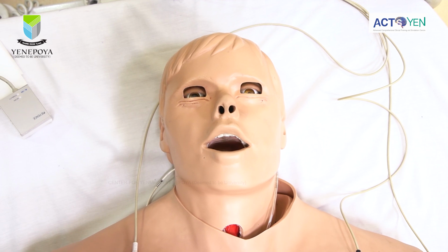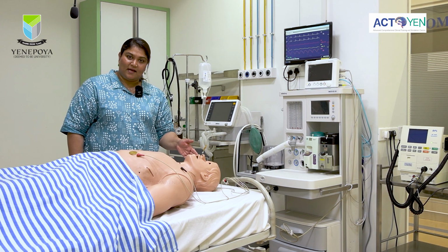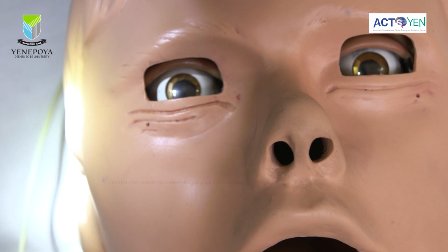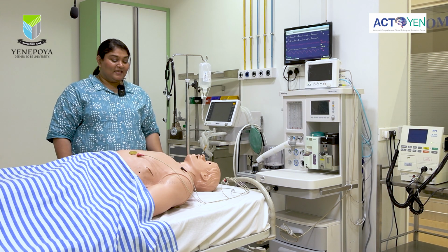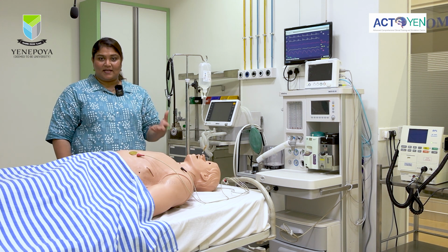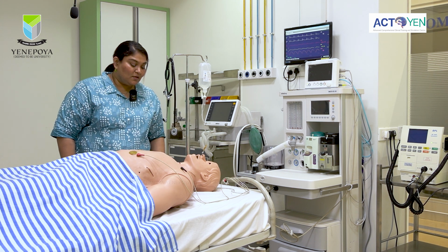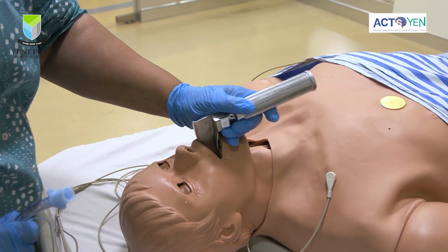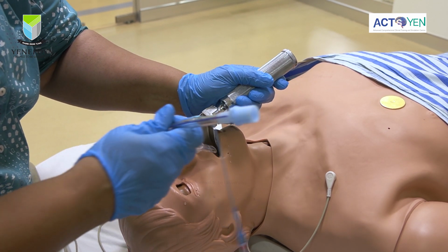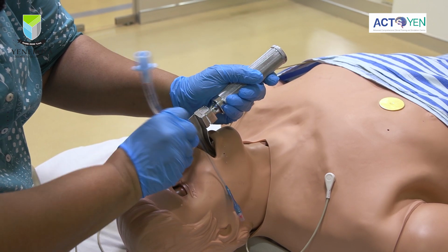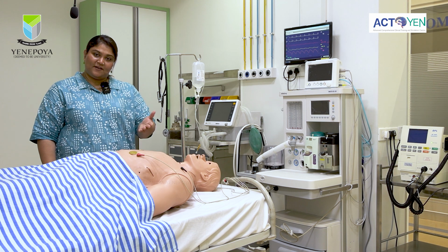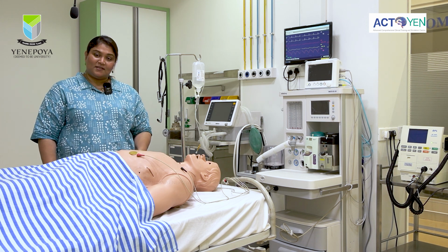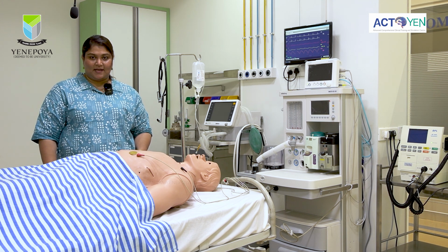HPS can blink, his eyes can be closed when he is unconscious, and interestingly we can also check the pupillary reaction of HPS. With respect to his airway, he breathes in oxygen and exhales carbon dioxide as we all do, and you can go for a tongue swelling or obstruct the pharynx and the larynx and create a difficult airway situation. With respect to the respiratory system, we can auscultate the different areas of the lungs and auscultate for rhonchi, for wheezing, for crackles and crepitations as well.